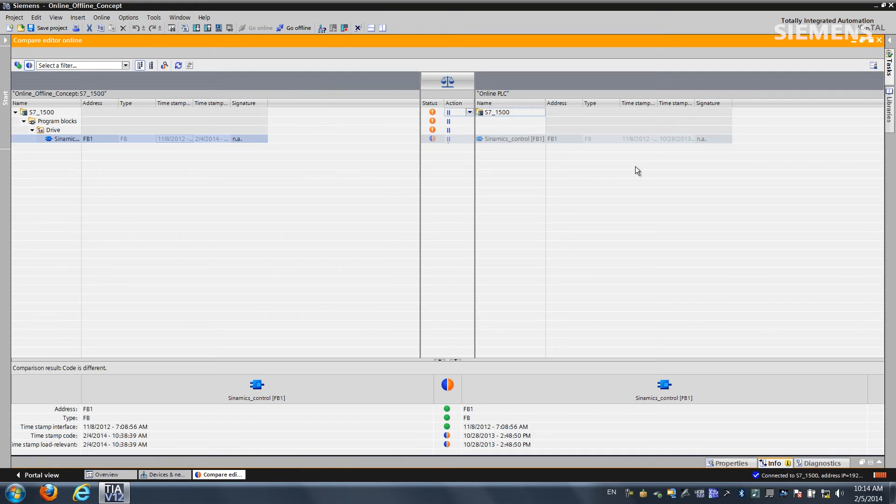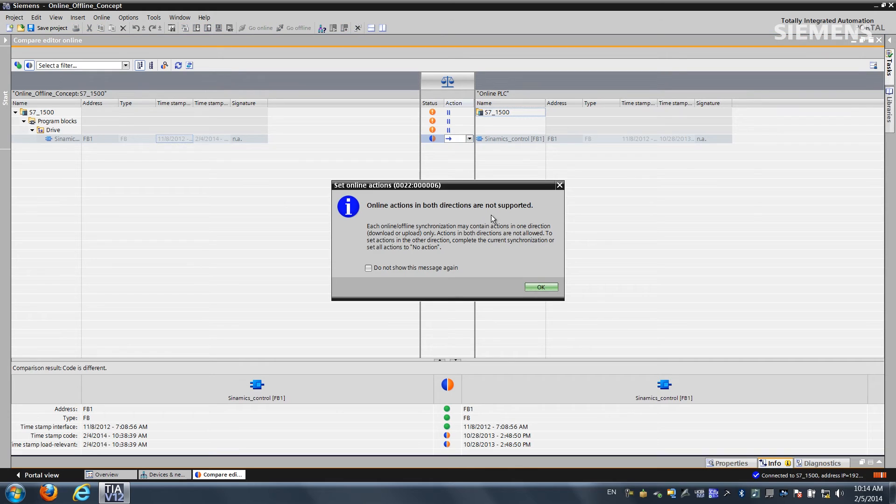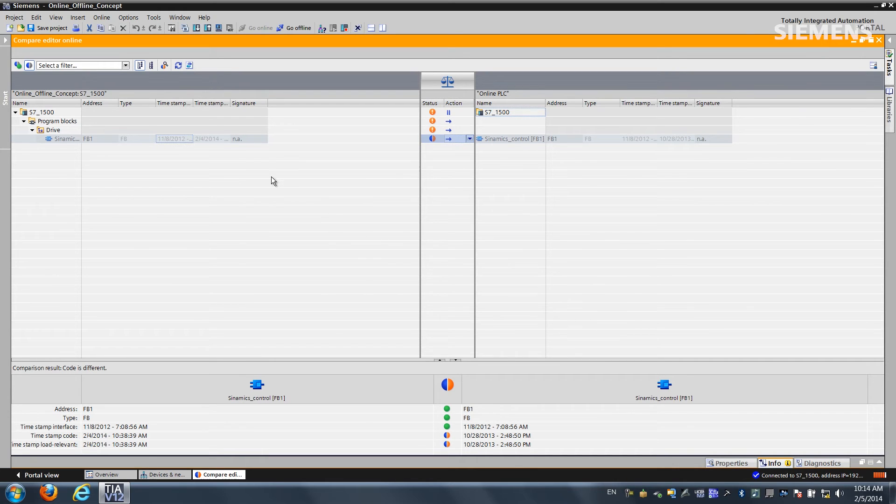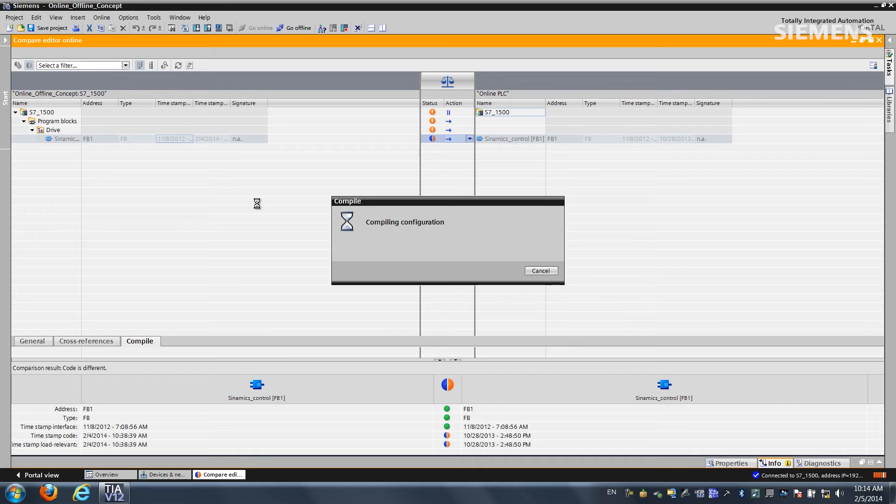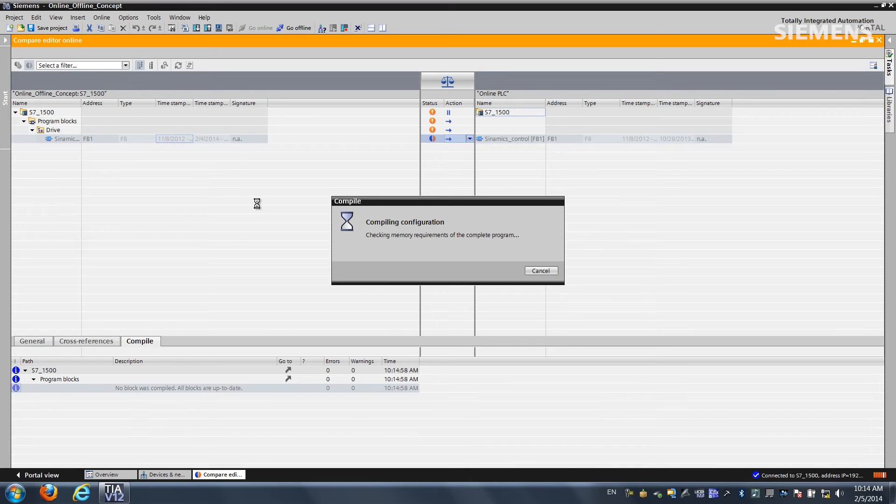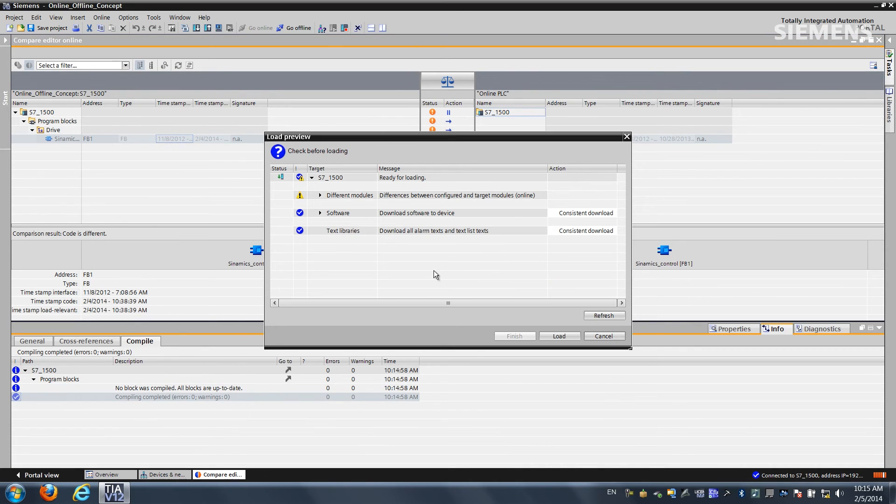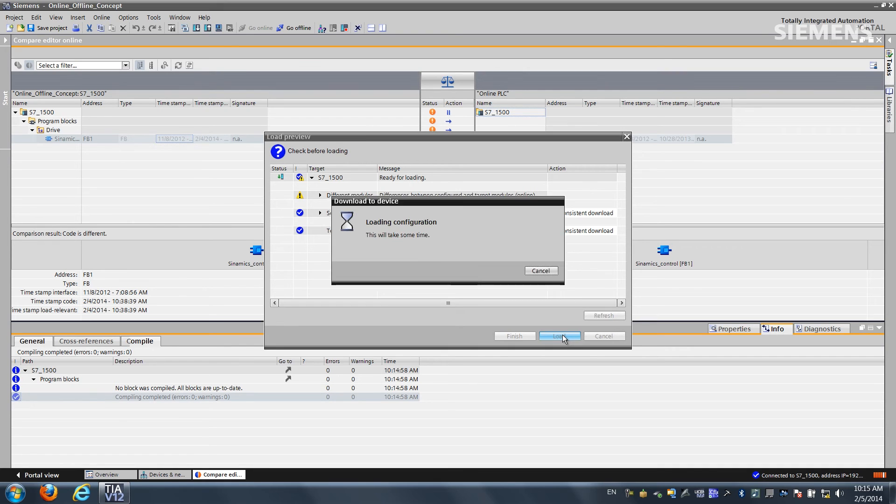What I want to do is actually close this out, give focus right here and choose download to device. Click OK and come up here and hit this execute actions. Now he's going to compile the fact I want to make this change. Now you see I have a consistency download so he's only going to load the actual delta difference. That is fine. Click on load.